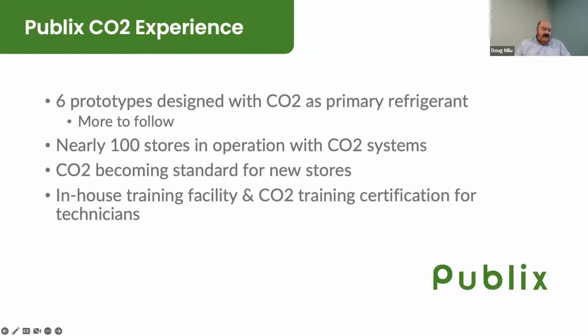We have right about 100 stores operating with CO2 as a primary refrigerant. We started this journey back in 2010, with low temp cascade CO2 systems operating as a direct expansion refrigerant with an HFC topside unit managing the evaporator condensers. Those were really key in our decision to move forward, because we learned about handling CO2, working through contractor issues, training, startup, and subsequent operational learnings with CO2 systems.